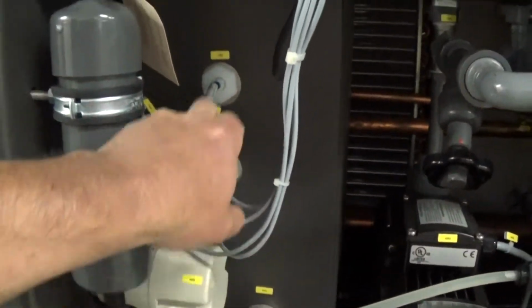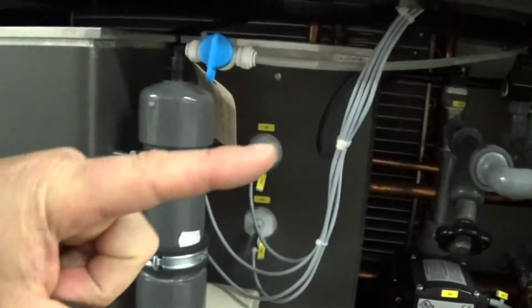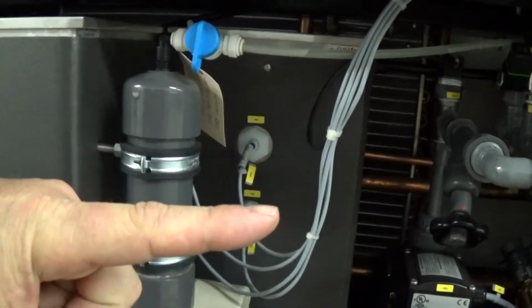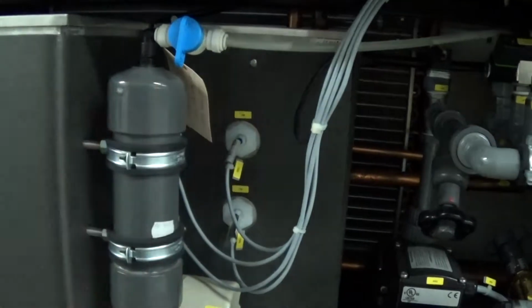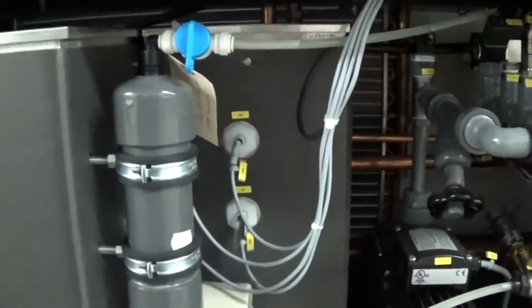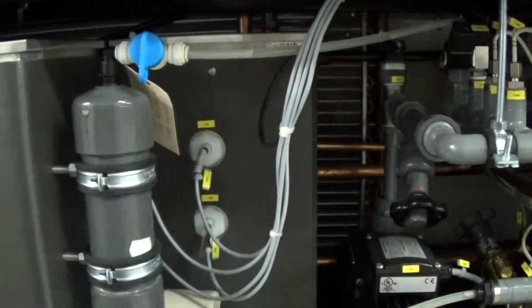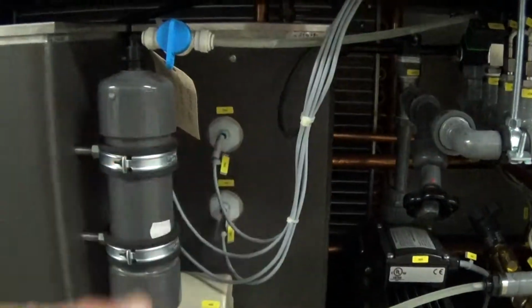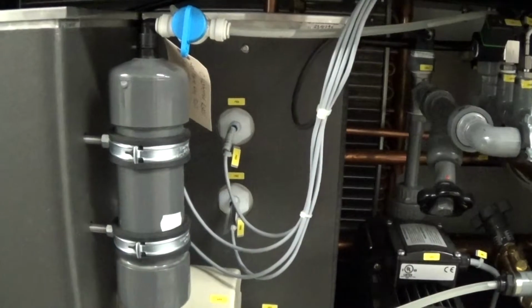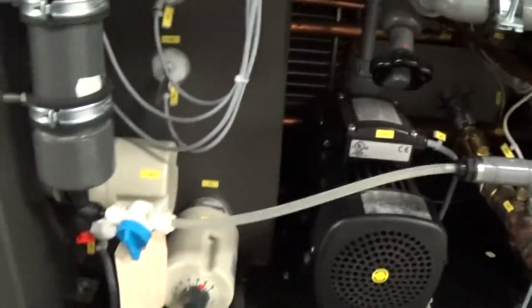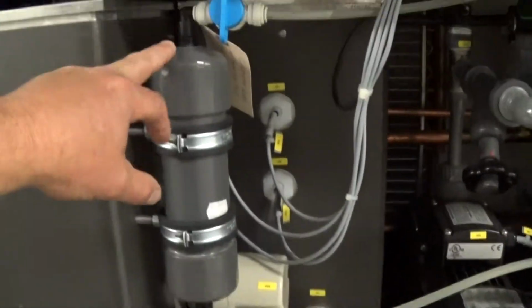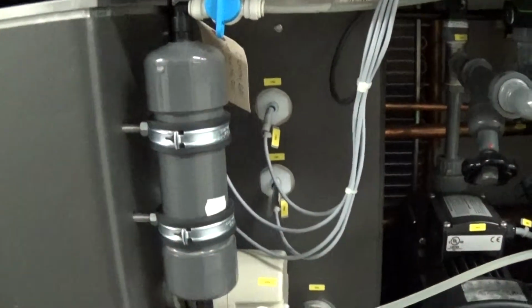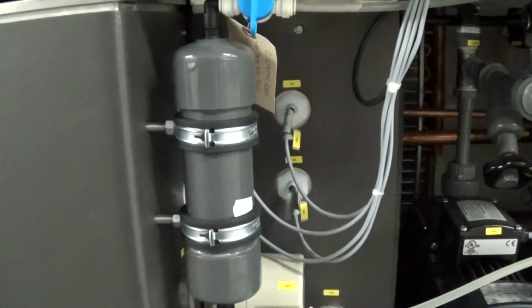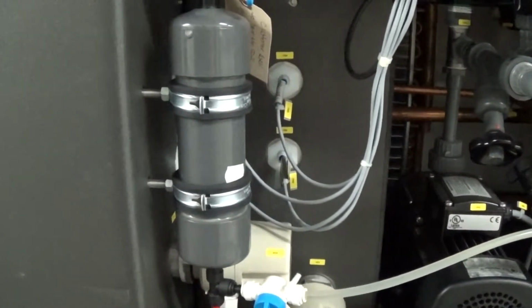Internally, behind my fingers here in the tank, are two little float level sensors. We have those, because those are still tied into the controls, those are wire tied in the open position. But no water or fluid is going to go through this circuit, and it's just easier for us to leave this stuff in there as opposed to removing it. So this pump here will never operate. Also, this little DI filter cartridge is just part of the smaller circuit. That's not going to be functional for your operation either.